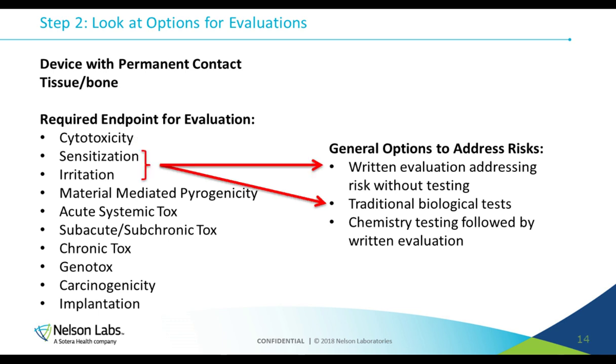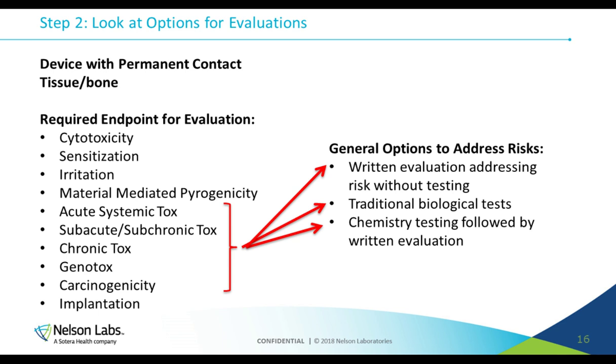For the next two, sensitization and irritation, this is the other part of the big three. These are two that regulators have been very clear in the past that they don't feel like chemistry testing followed by a written evaluation would be sufficient to address them. So for those two, we either recommend doing the traditional biological test or doing a written evaluation if it's a very well-known material. For material-mediated pyrogenicity, we really recommend the traditional biocompatibility test.